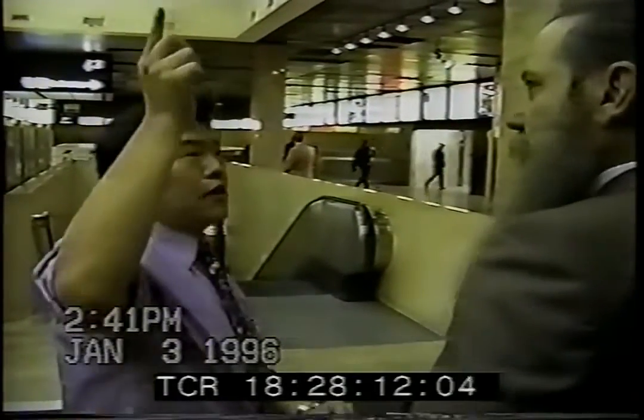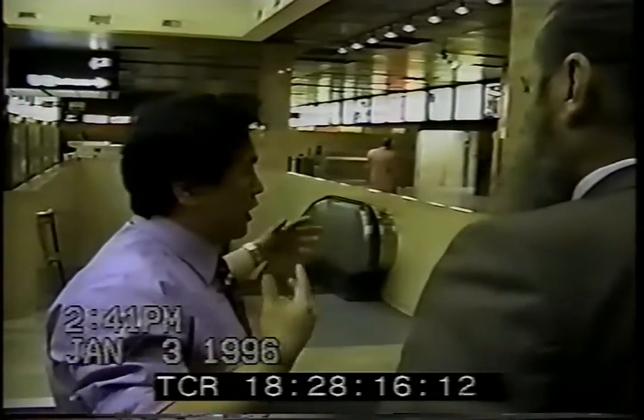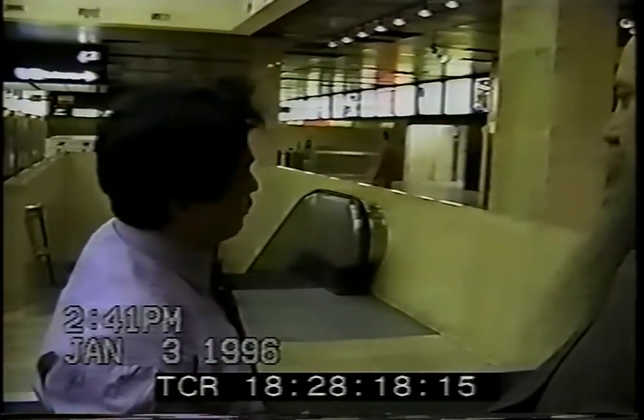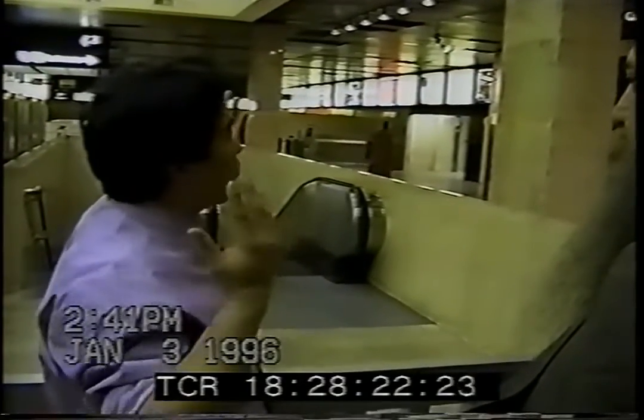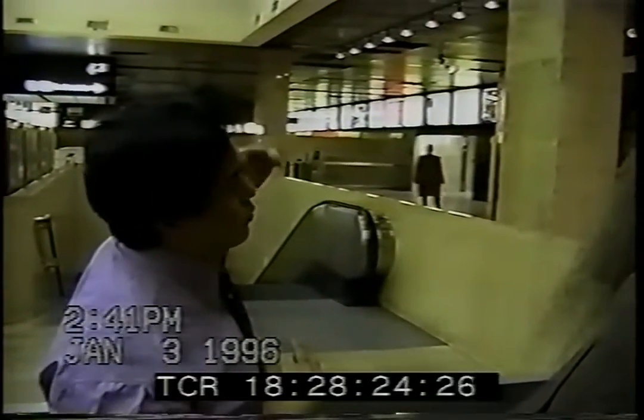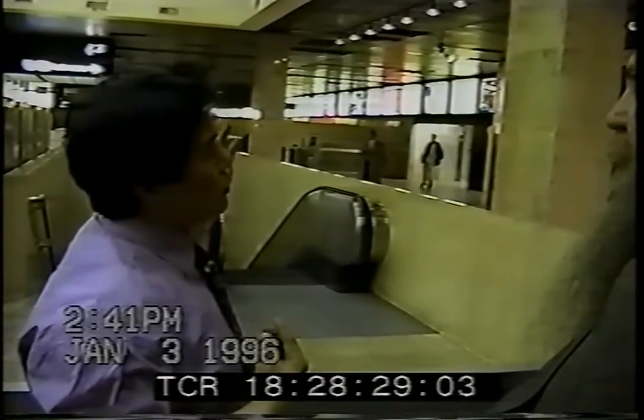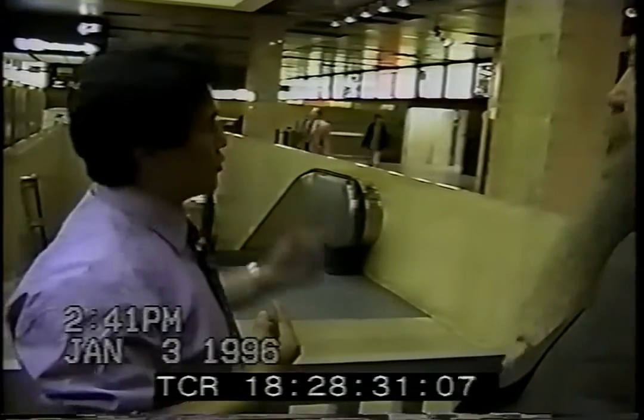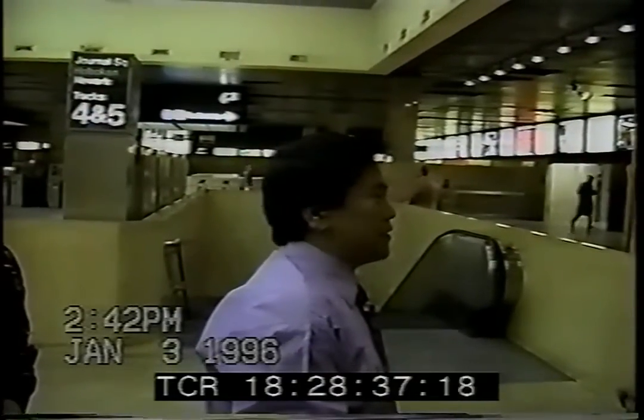Right. This is only more of a secondary containment. If you cannot control the smoke because of the stack effect you have here, the smoke is going to come straight out from here. You might get down to a point where you want to exhaust the smoke, but this will not be automatically turned on until the smoke level is so high that we turn this on. This is your incidental spill. Exactly. They're hoping to control it.